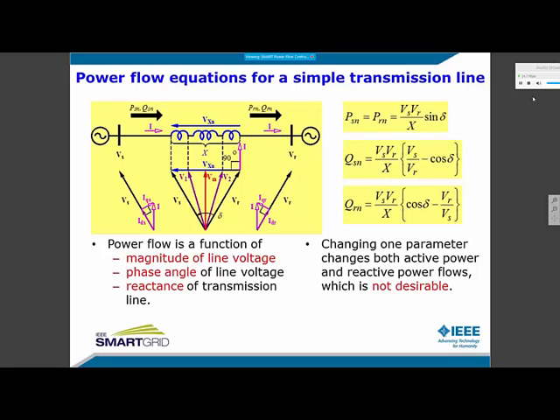Therefore, the transmission lines are never optimized to carry the highest possible amount of P that generates the most revenue with minimal Q. To transmit P and Q flow independently, we need to control two parameters. The phasor diagram shows that both the source and the load supply Q that is absorbed in the inductance of the line when P is transmitted from source to the load.